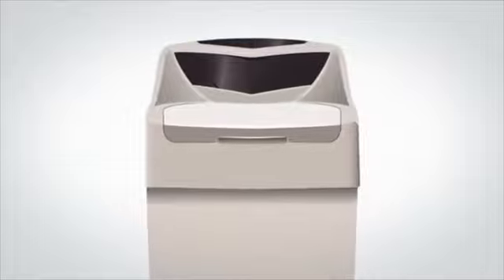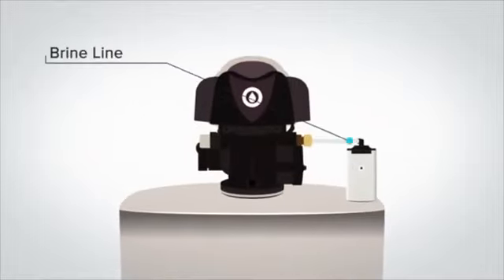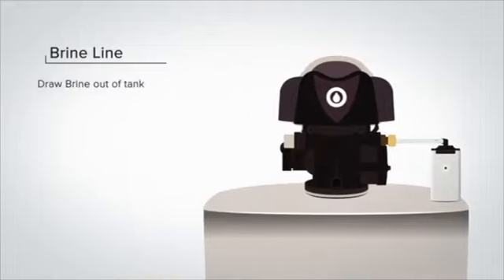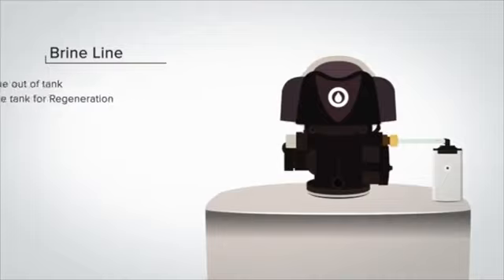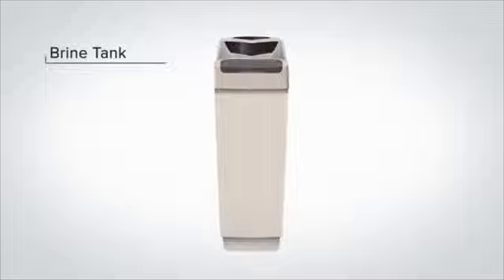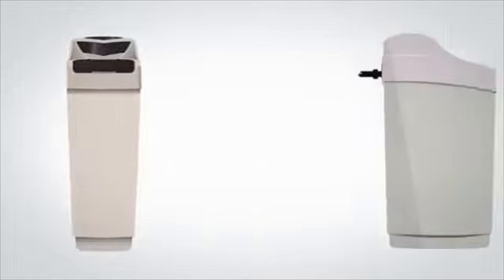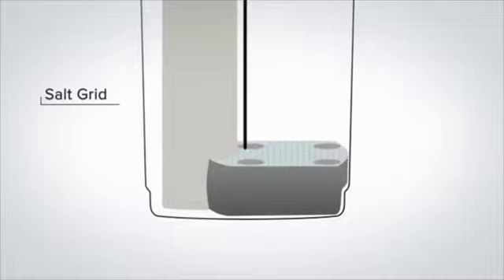Running from the softener control valve down to the brine tank is the brine line. This tube has two functions: it's used to draw the brine out of the brine tank, and it's also used to refill the brine tank for future regeneration. The final component is the brine tank. The brine tank is where salt is added to the system. All Drop brine tanks include a salt grid at the bottom of the tank. The salt grid helps to keep the salt from bridging.